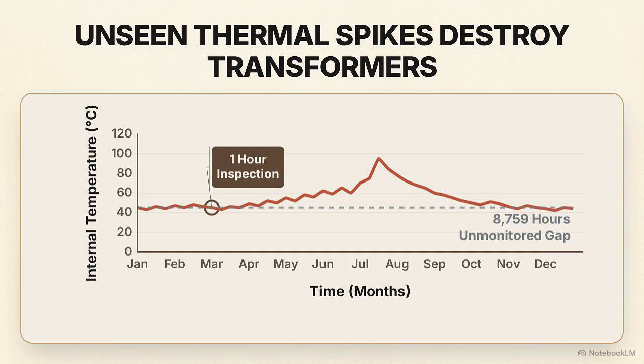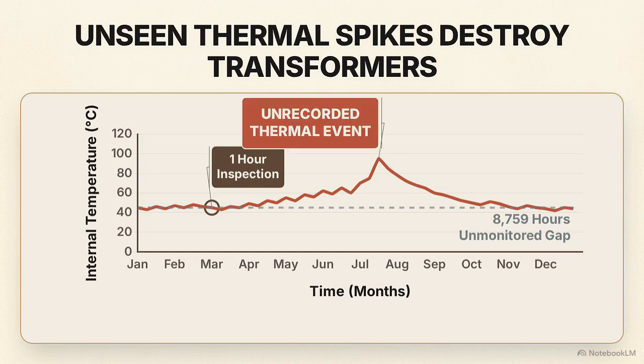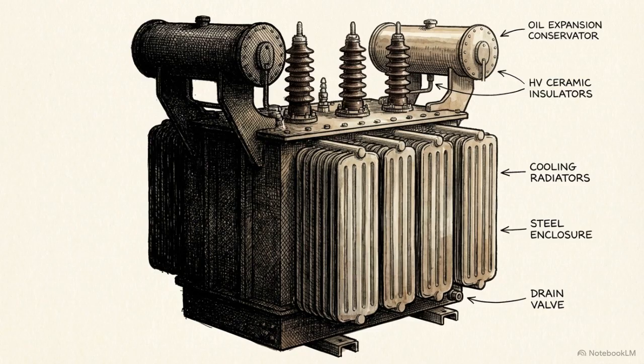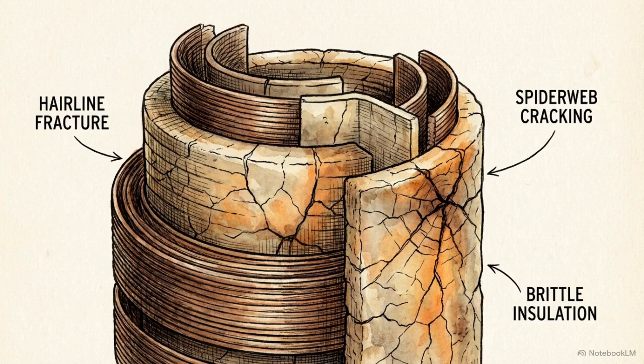A facility experiences sudden load fluctuations, a surge in production, or an intense ambient heat wave. The transformer's temperature spikes violently upward, sustaining damage that goes entirely unrecorded by the annual check. Relying on a single yearly snapshot to verify the health of mission-critical infrastructure creates a temporal blind spot. Within that unmonitored window, cumulative damage incubates unnoticed until the system fails.